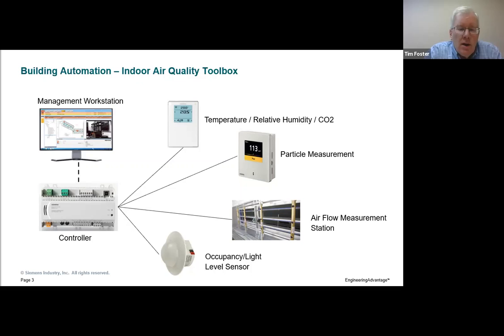So moving to indoor air quality, you can see I've listed some devices there. And this isn't meant to be a technical deep dive, other than to say that temperature, relative humidity, carbon dioxide sensing, particle measurement, airflow stations, occupancy, lighting level switches, all of that data can be brought into the building automation system. We can develop a unique sequence of operation, and we can control the building accordingly. And the lines you see aren't necessarily literal lines, where it means that say a particle measurement sensor needs to be wired back and landed on a controller terminal. That data can be acquired in a variety of different ways, including from the cloud, from different systems, subsystems within the building.